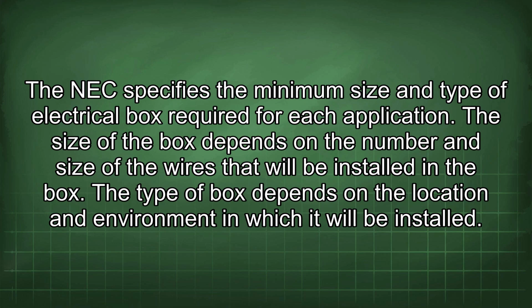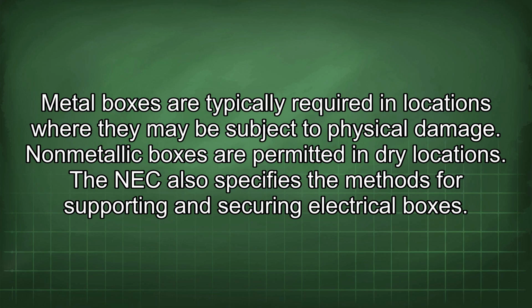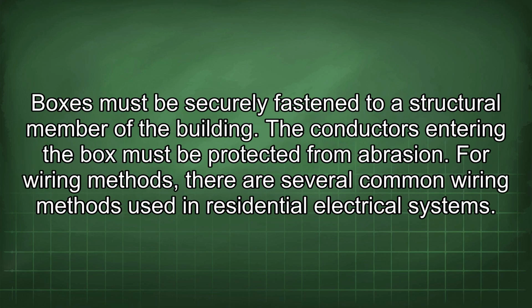The type of box depends on the location and environment in which it will be installed. Metal boxes are typically required in locations where they may be subject to physical damage. Non-metallic boxes are permitted in dry locations. The NEC also specifies the methods for supporting and securing electrical boxes. Boxes must be securely fastened to a structural member of the building. The conductors entering the box must be protected from abrasion.